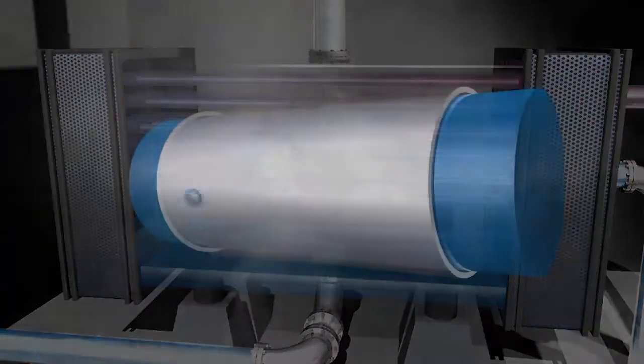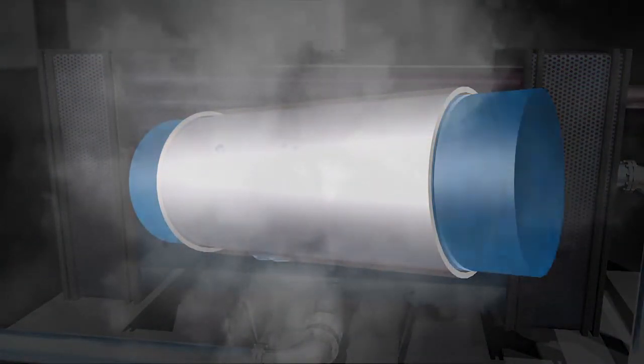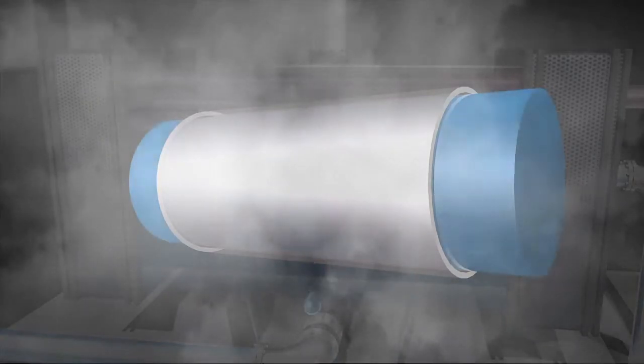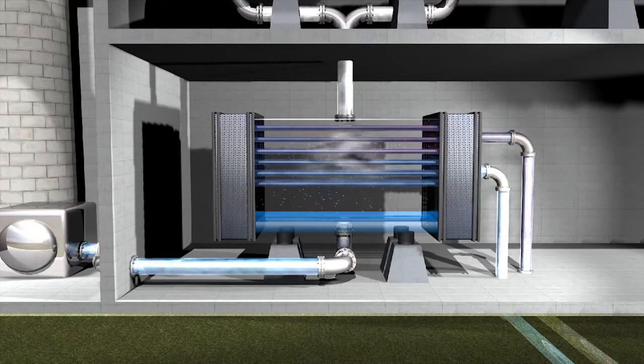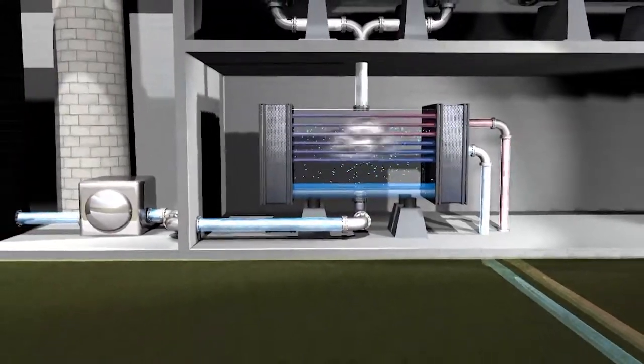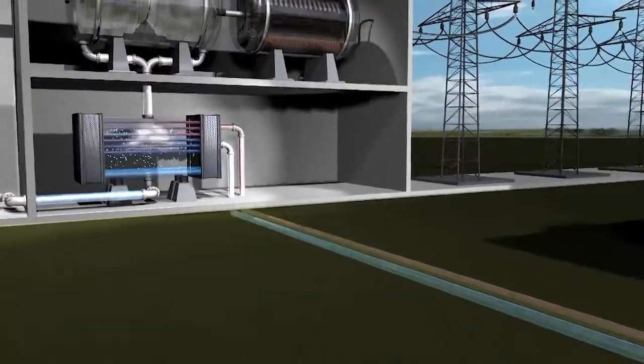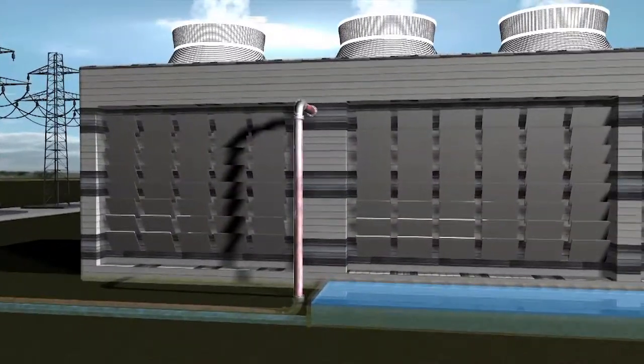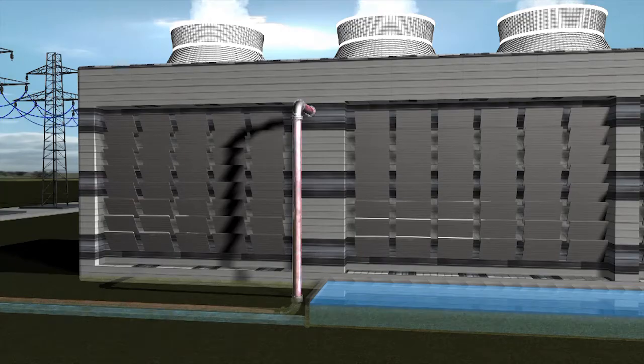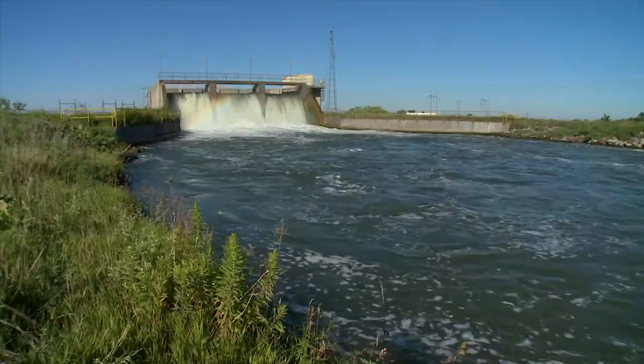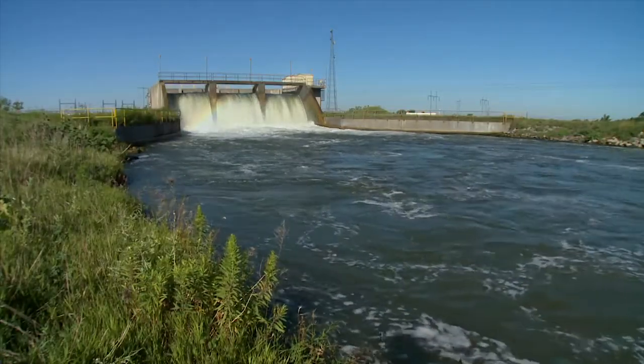But where the radiator in a car uses air, the condenser uses cold water. Cool water runs through the condenser within thousands of tubes. The steam passes around the outside of those tubes and is cooled and condensed back to water. The cooling water gets heated as the steam is condensed. Before it can be reused, the water needs to be cooled down. In some plants, that happens in a cooling tower, a structure containing many series of waterfalls that cool the water by evaporation. In other plants, the heated cooling water flows to ponds where its heat is dissipated.